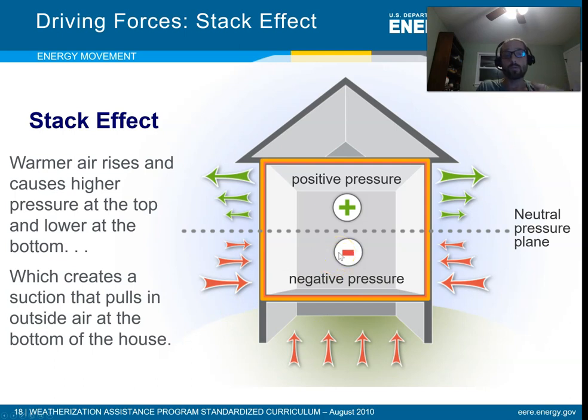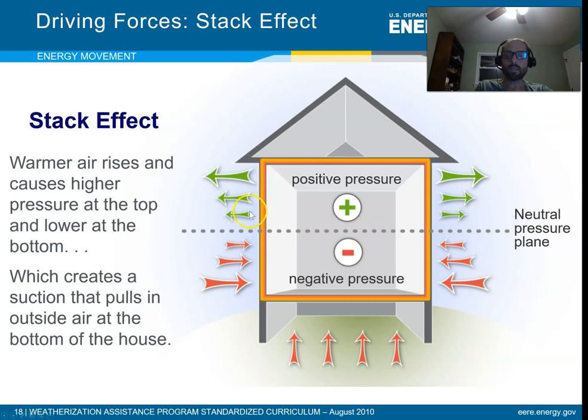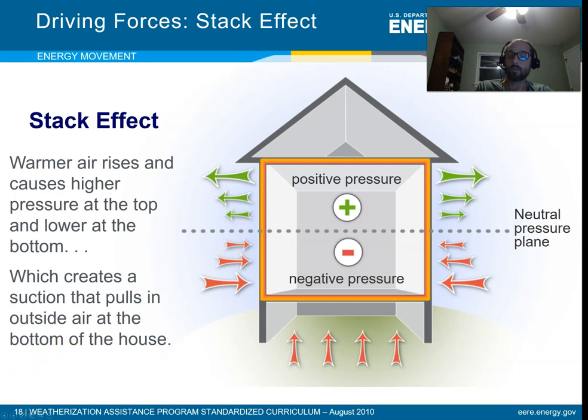You end up with two broad pressure zones: a positive pressure zone on the upper side of the building and a negative zone on the lower side. Where those two meet is called the neutral pressure plane — a two-dimensional flat surface where there is neutral pressure. The arrows in this drawing indicate the magnitude of the delta P in each zone — smaller arrows mean lower pressure, bigger green arrows mean more positive, and bigger red arrows mean more negative.